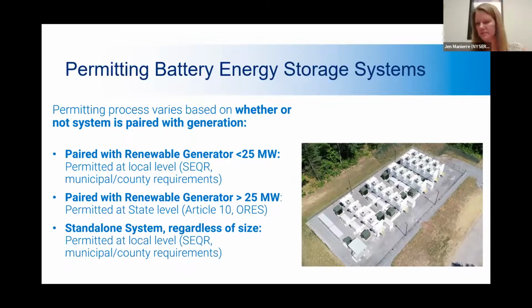This is a little bit of a repeat slide from what I said before, but just remember, large systems are permitted at the state level, smaller systems are permitted locally, and then this funny 20 to 25 megawatts can go either way. And that's for the renewable generators. Battery energy storage, if it's paired with a renewable generator that's being permitted at the state level, gets permitted right along with it. But if it's standalone, no matter how small or how big it is, it's going to be permitted at the local level.